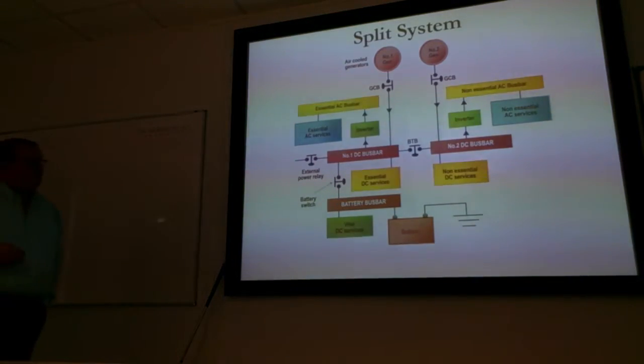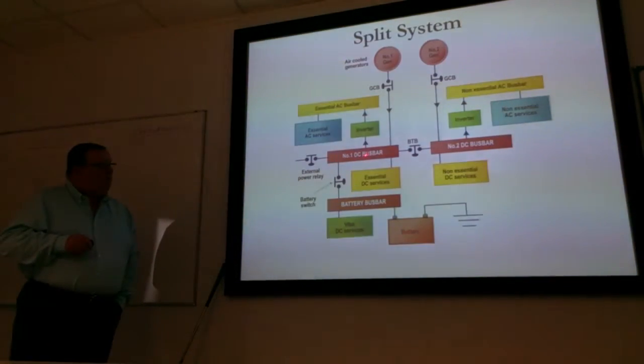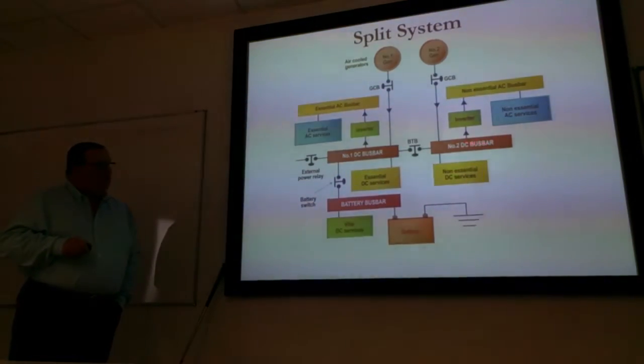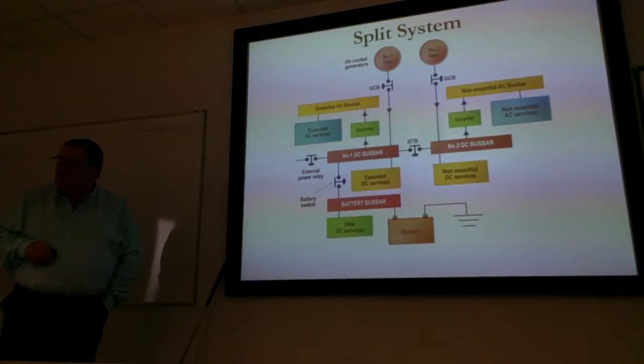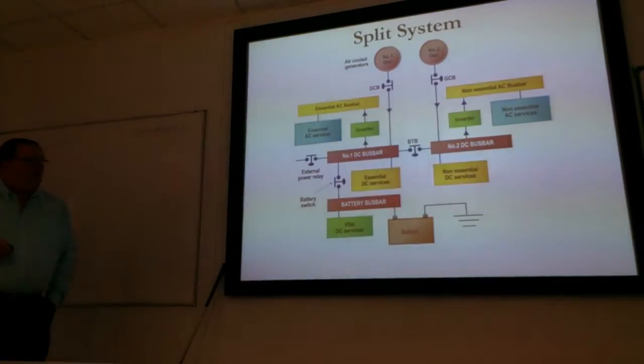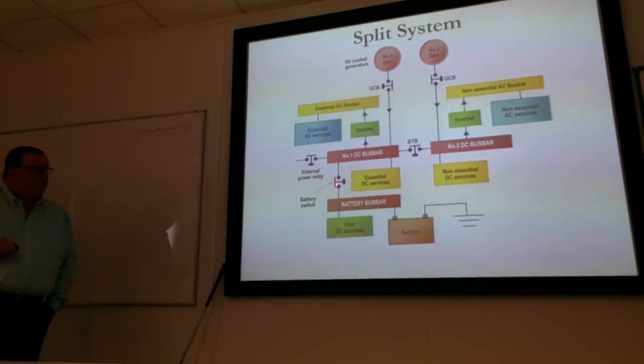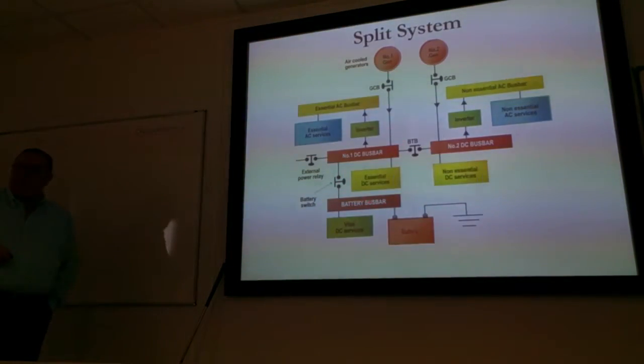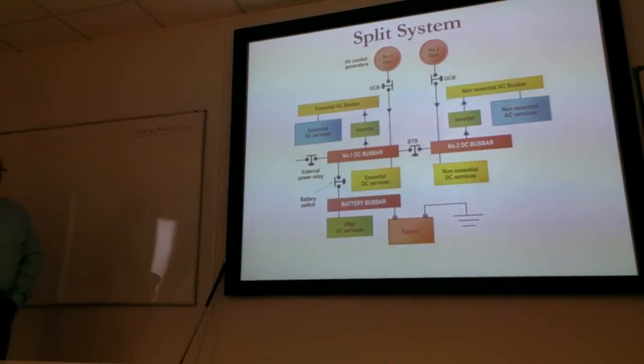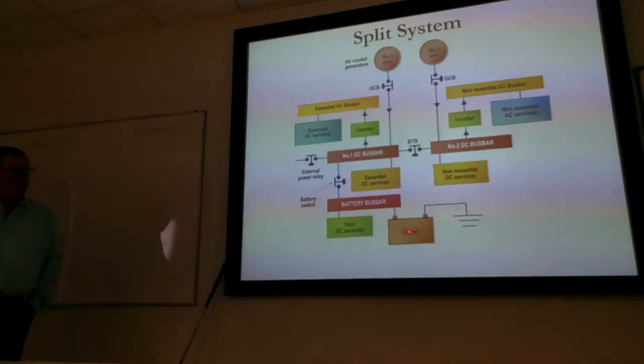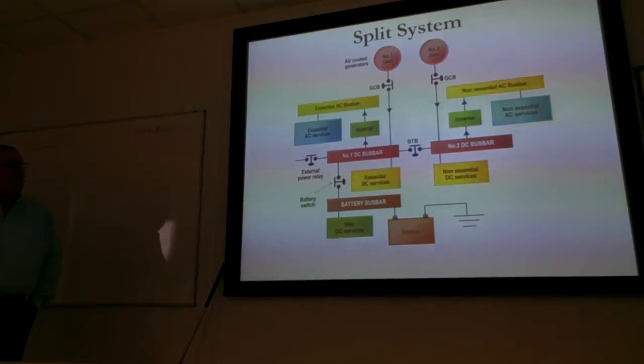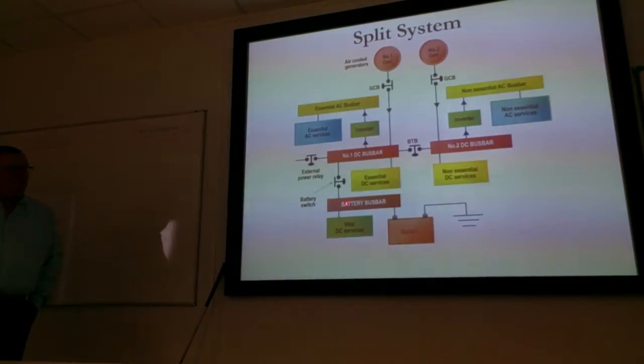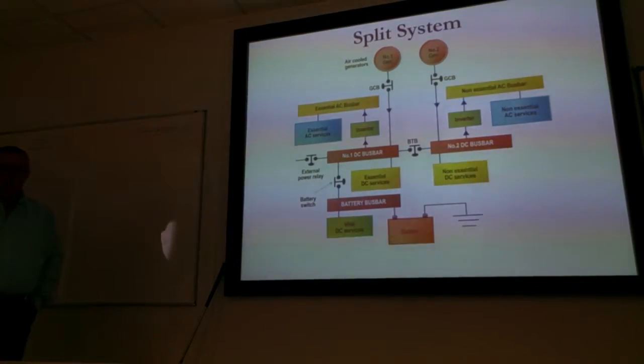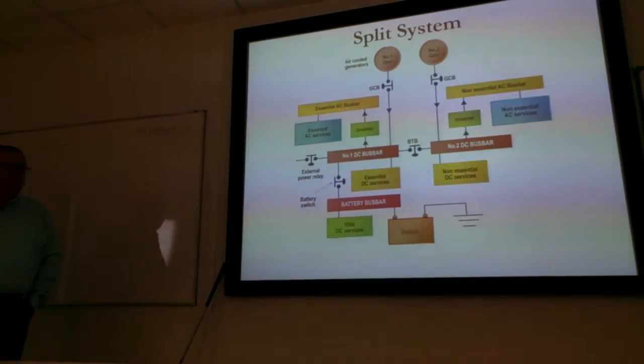Okay, staying with DC then, the number 1 DC bus provides essential DC services on that bus bar, and from the number 2 bus bar we are providing non-essential DC. Coming further down from the DC bus to the battery switch takes us to the battery bus bar. You remember that can also be called the hot bus or the back bus. From that we connect the battery and the vital DC services. So in the event of both generators being offline, that bus bar will be powering the DC services because they're hardwired direct to battery.